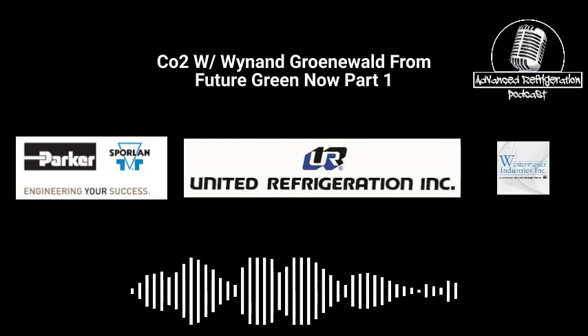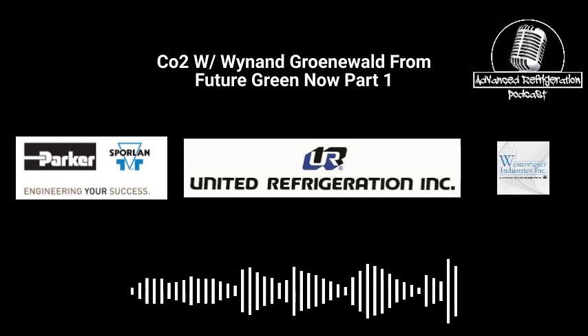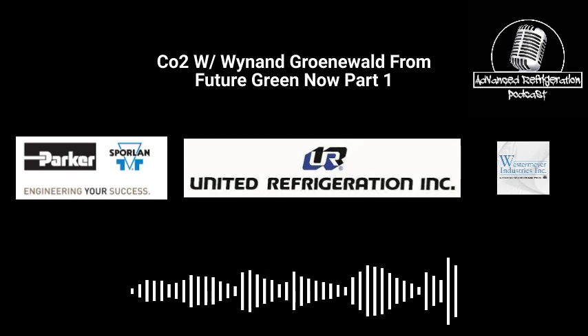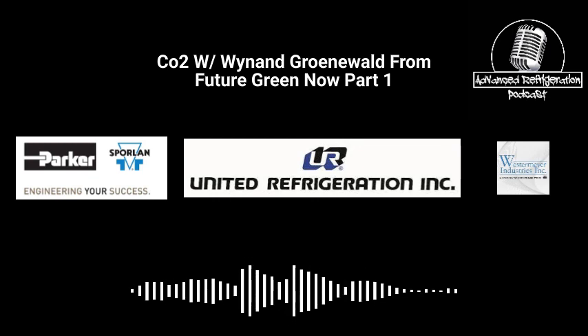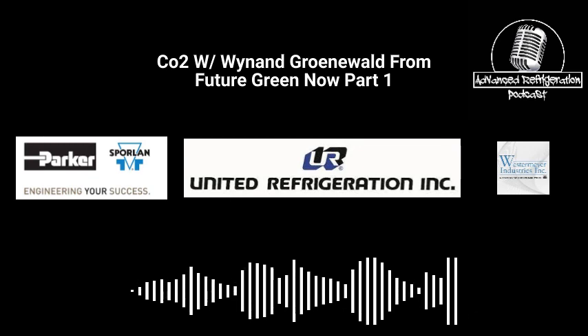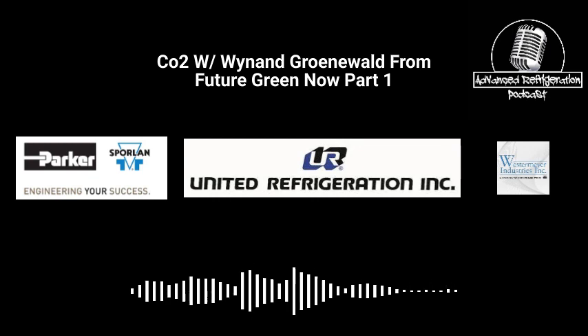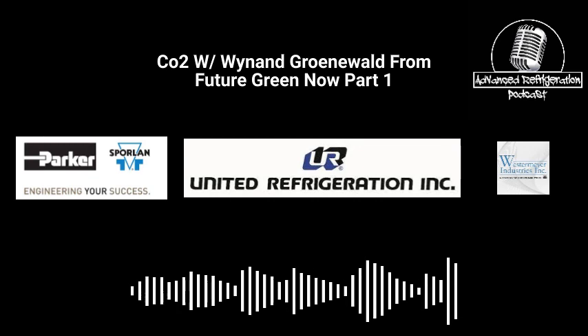Nah. We've always done first in, last out. So the first case to get liquid in is the last case to get suction out, or the vapor return line out. Just like we would pipe glycol, that's how we've done it. Whatever case gets fed first, the return line is the farthest away. I don't really think it does anything, since all those cases have solenoids on them. They're going to cycle on and off as needed for temperature, but most of the time that stuff just floats off the vessel.